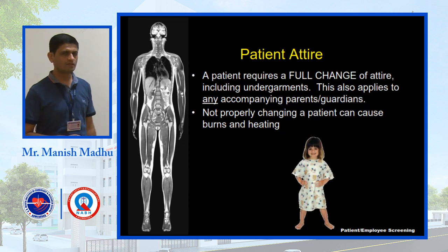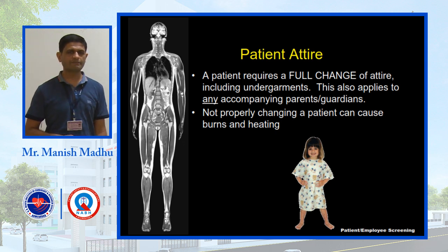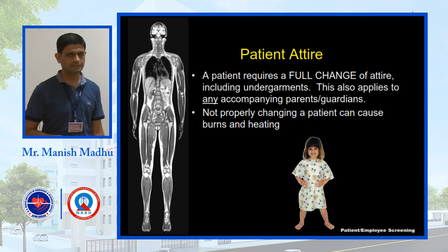Patient attire. How to attend to the patient? A patient requires a full change of attire including undergarments. This also applies to any accompanying parents or guardians. Not properly changing a patient can cause burns and heating. So whenever taking the patient, he has to change all his clothes including undergarments, and family members should also be changed and then allowed in the MRI room. Otherwise it may cause burns or heating.